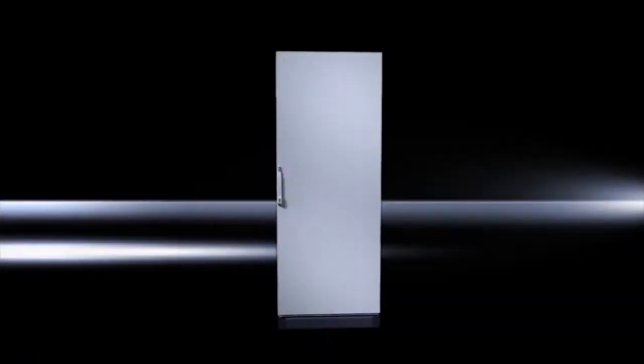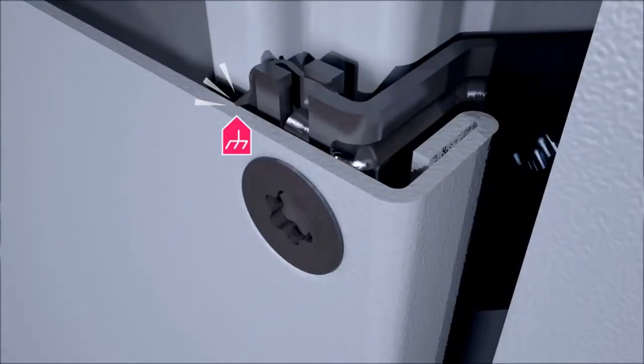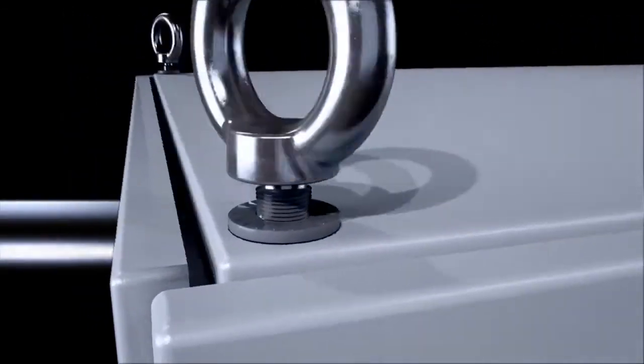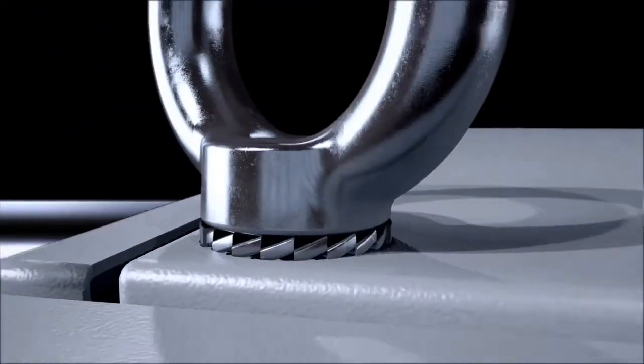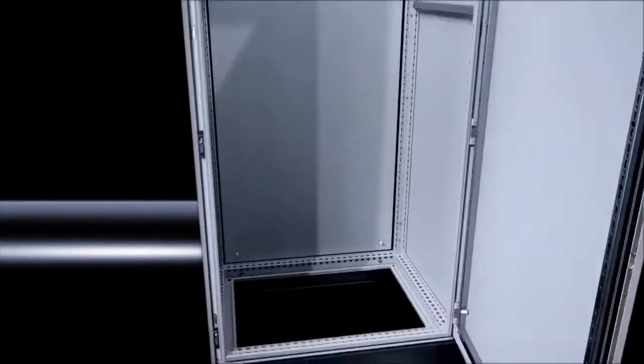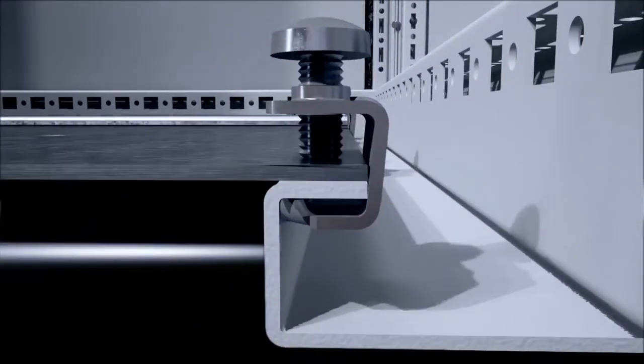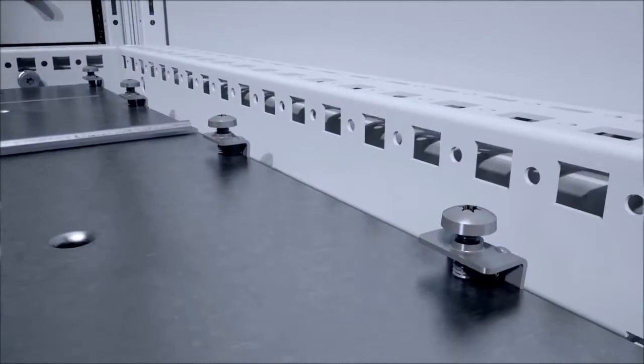One of the biggest concerns that our customers have is grounding of electrical enclosures. One unique benefit of the TS8 is right off the factory floor — the standard TS has all the external panels grounded back to the frame. This eliminates the need and the time and labor for running ground straps in the field. The other benefit is in EMI/RFI environments, this cabinet adds an additional layer of protection, further reducing those interferences by a ratio of 1 to 10.